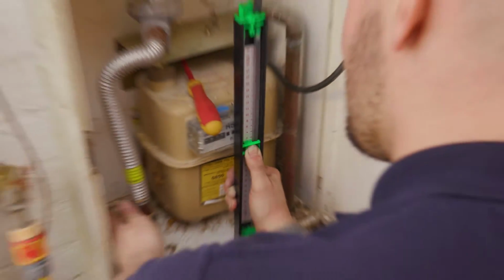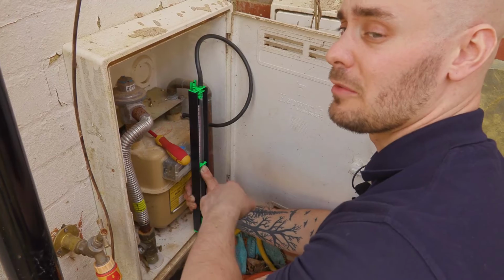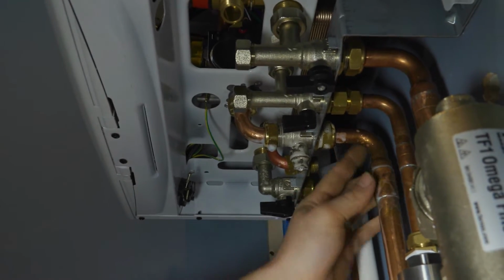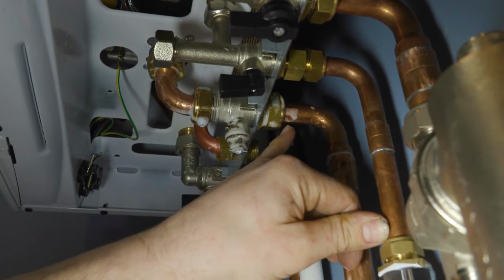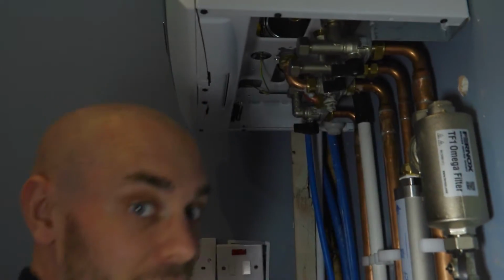This is just to ensure that this valve is working correctly, there's no pressure going. Once I turn it off again, that there's no gas going up and into the meter when it shouldn't be. So what's happened is, we've gone to test the gas, and the back nut there wasn't tight. So I've put LDF, which is leak detector fluid, around the join, and there's gas seeping out. The leak detector will bubble up, which exposes the leak. So we've remedied that, we've tightened it up, and now we're going to go and check.